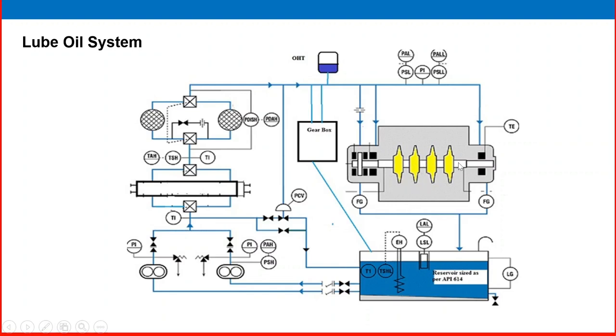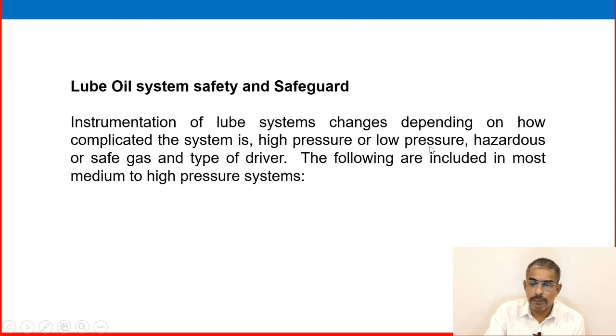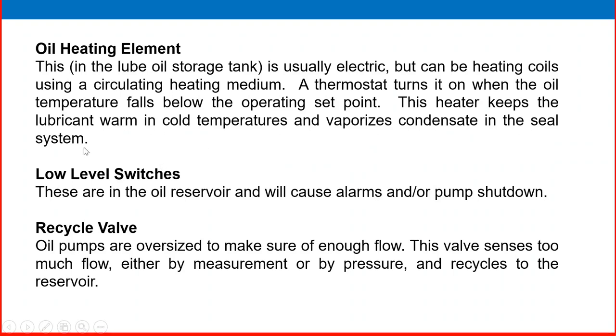Instrumentation of the lube oil system varies depending on system complexity, pressure level, whether the gas is hazardous, and the type of driver. General details include: an oil heating element in the lube oil storage tank — usually electric but can use heating coils — controlled by a thermostat that activates when oil temperature falls below the operating set point, keeping the lubricant warm in cold conditions. Low level switches maintain a minimum oil level in the reservoir.